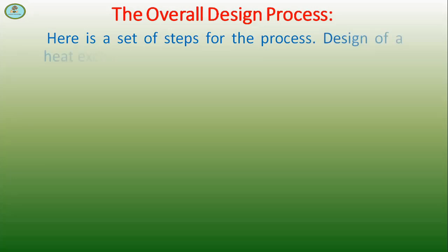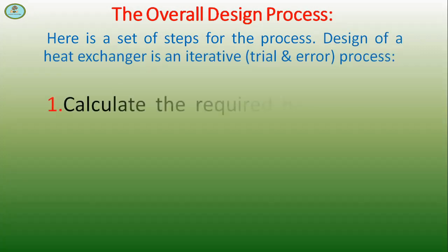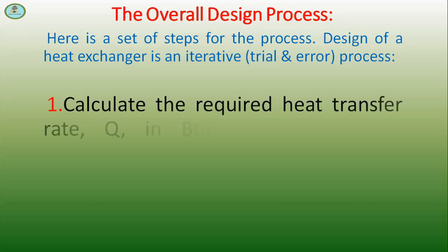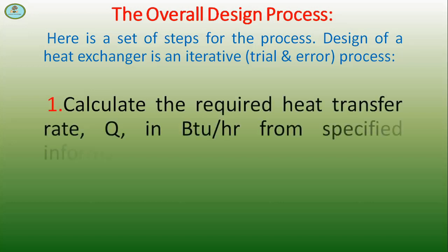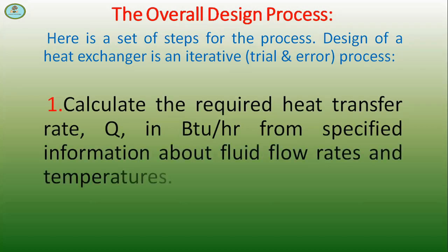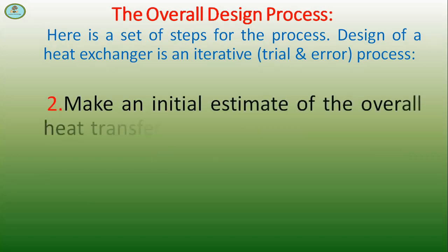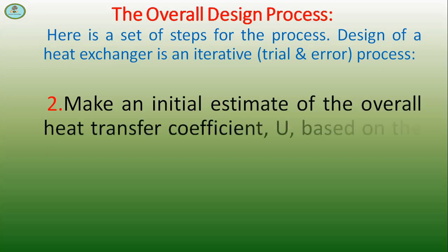Here is a set of steps for the process. Design of a heat exchanger is an iterative trial and error process. First is calculate the required heat transfer rate in BTU per hour from specified information about fluid flow rate and temperatures. Second is make an initial estimate of the overall heat transfer coefficient based on the fluids involved.